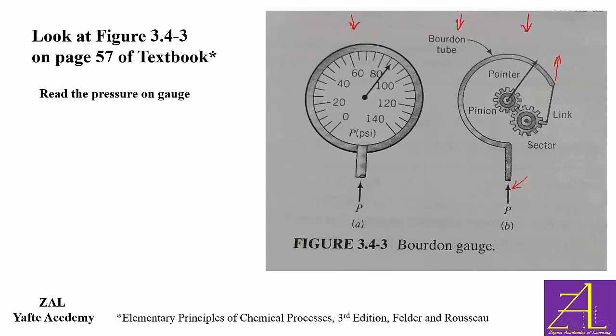Because the tip is connected with a metal link to a gear which is called sector, it tends to make this gear move counterclockwise. And this gear in turn is connected to a second gear which is called pinion. As a result, it makes the pinion move clockwise and will move the pointer clockwise as well.